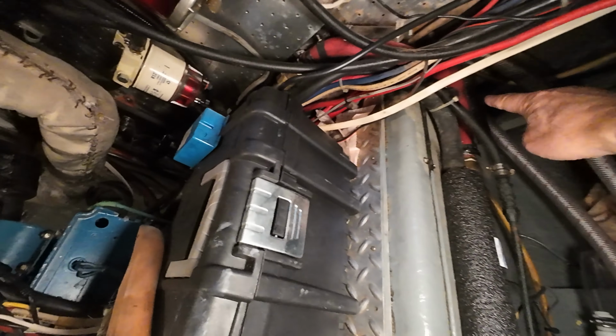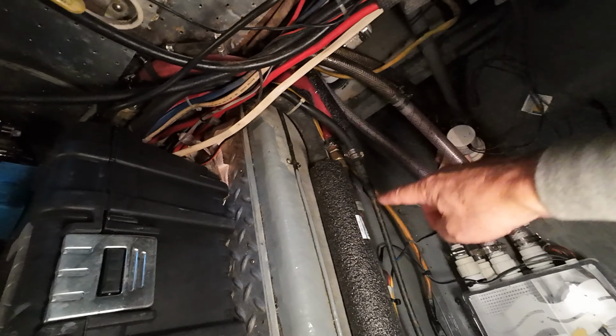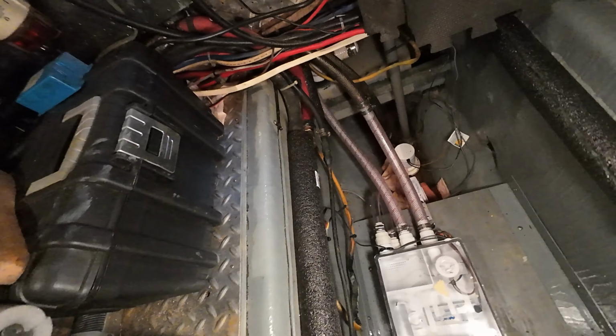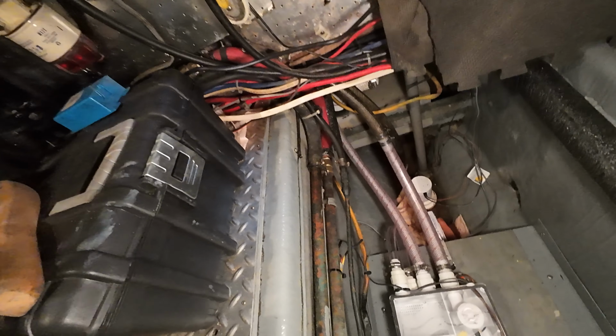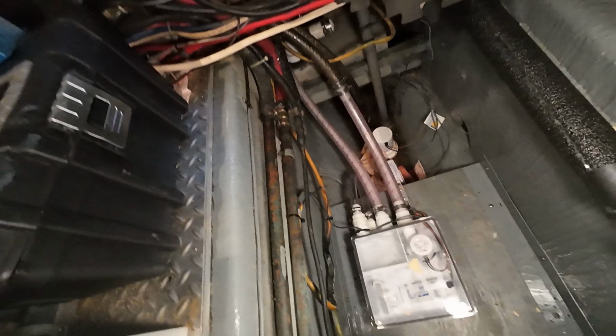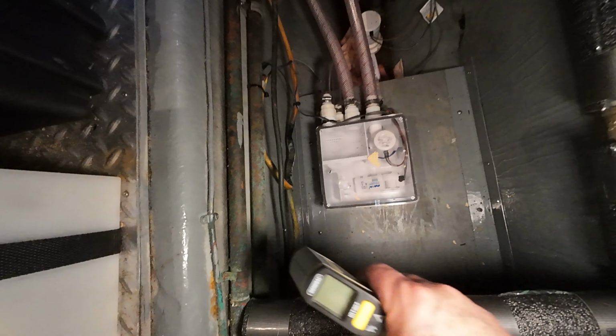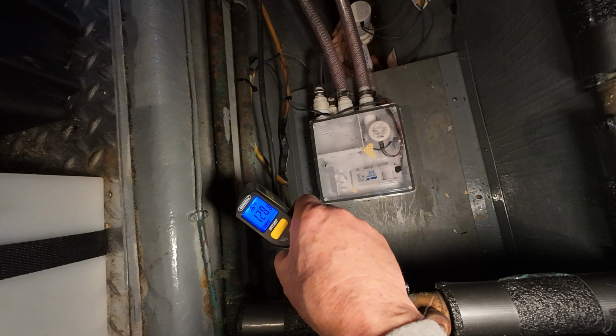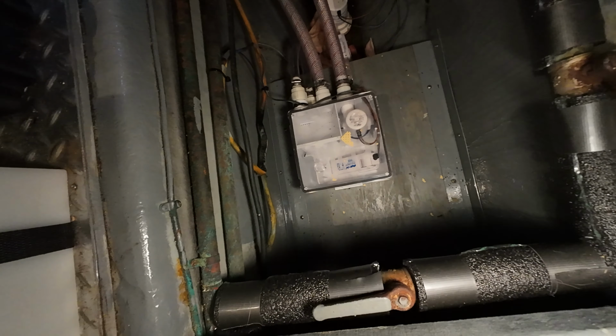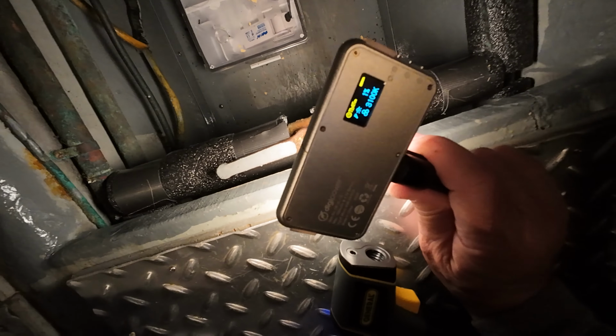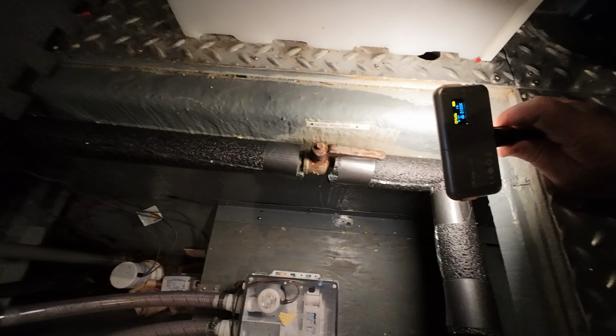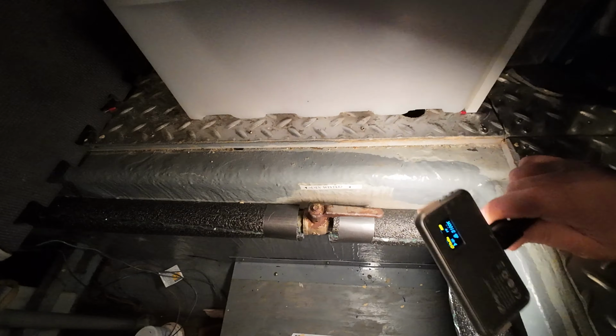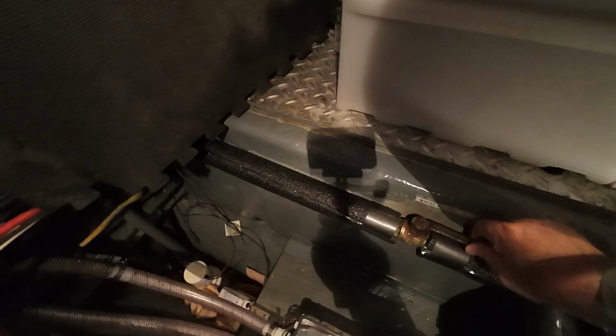These two hoses that we see over here, this one, the red one, and this one, the black one, are the ones that are coming directly from the pump. They're both hot. Okay, let's just see how hot they are. 128 degrees, 130 degrees. Then this one has a T in it, and it has this valve right here and this valve right here. This one says open in winter. So that's got to be open, right?